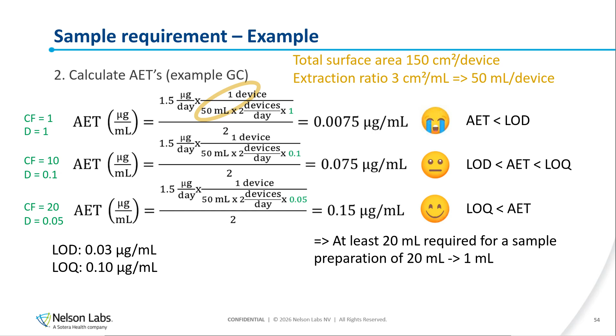So now we can determine the required volumes. In case of an exhaustive extraction, we need an exhaustivity determination, as explained in the first part. This will already require a certain amount of samples. And then we have the final extractions. And also for exaggerated extractions, this is very similar. This is mainly based on this concentration factor that we just determined. And with our example, we had 20 milliliters required, but we have an extraction ratio of 3 centimeters squared per milliliter, meaning we already need at least 50 milliliters for one sample. So yeah, we already have 50 milliliters.